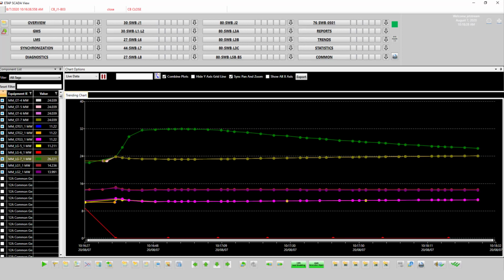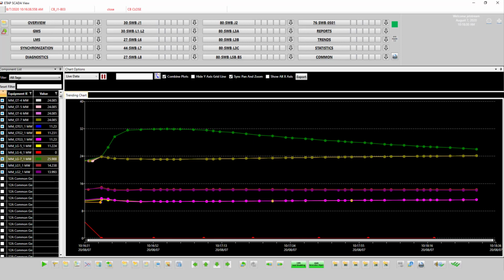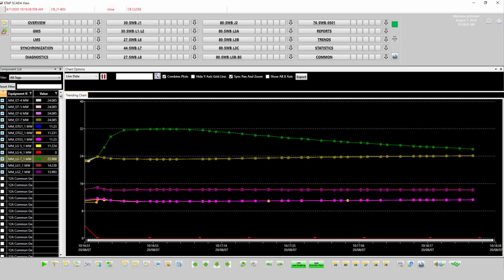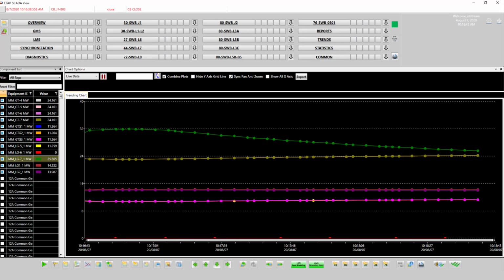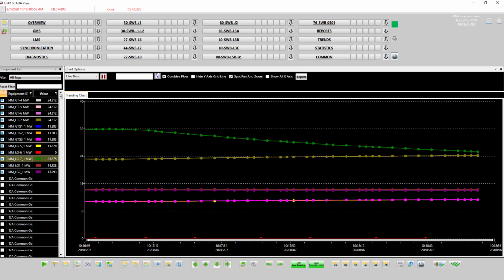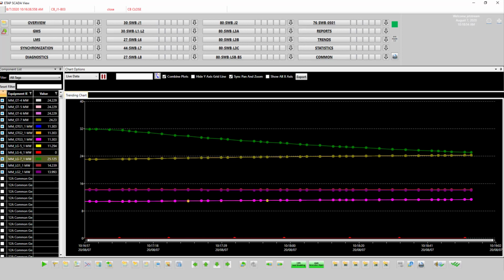3. How the trainer can override these interlocks on an ad hoc basis. 4. How the trainer can inject trip signals and other ad hoc commands. In this case, an overcurrent trip was injected into the system, which resulted in a CB trip and generator to go offline. And lastly, 5. How third-party controls can be configured in the OTS environment to provide the trainee a realistic understanding as to how the system actually behaves dynamically, giving the operator a crucial insight into the real-world environment.